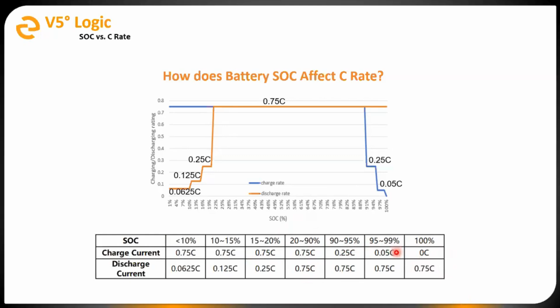So what's happening here between 90% and 100% is basically the batteries are calibrating internally, they're balancing their cells, they're calculating their state of charge. So what you'll see is sometimes very quickly during the day when we're charging, we hit that 90% value, but then sometimes to get from 90% to 100, the process is a lot slower. Again, just because the battery is doing things internally to balance out, and then of course because the charge current is reduced.